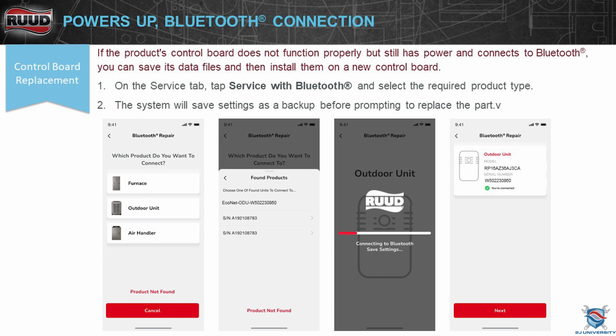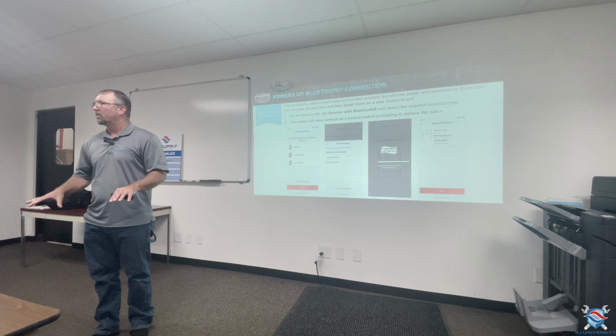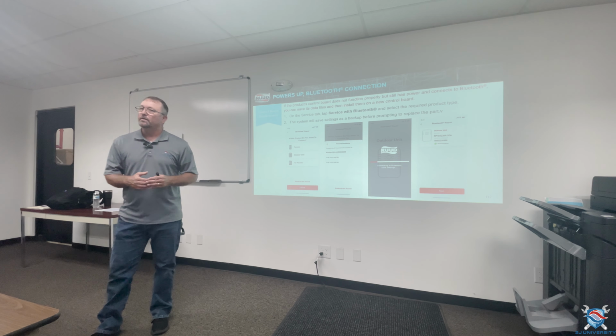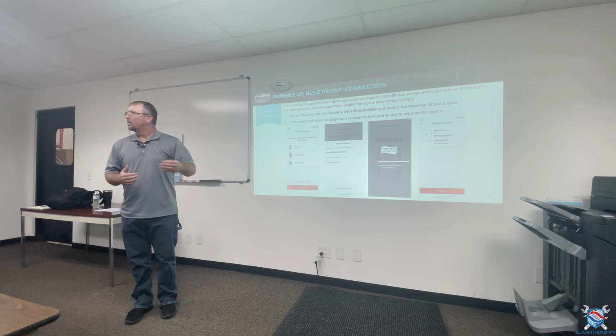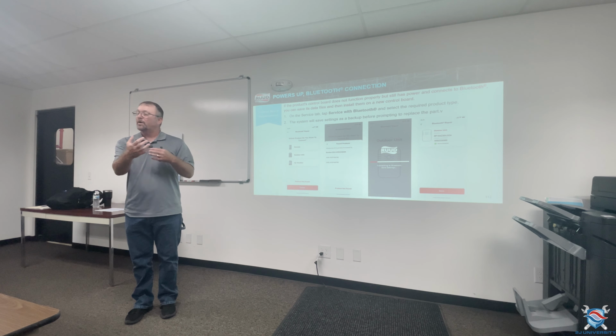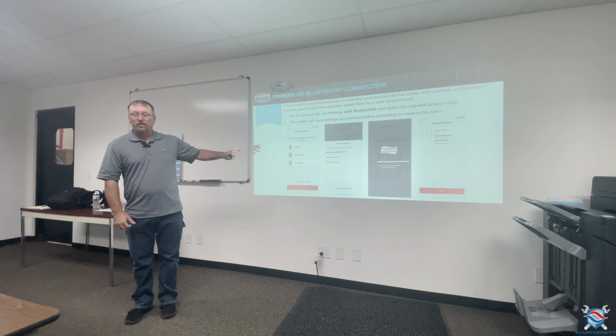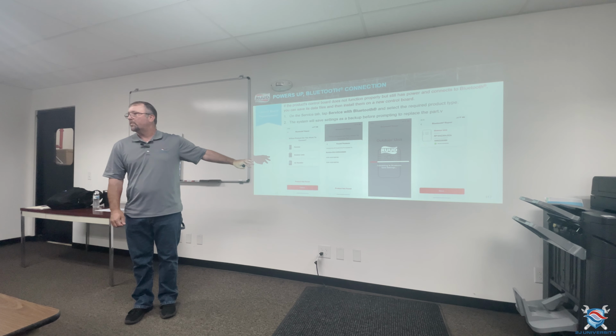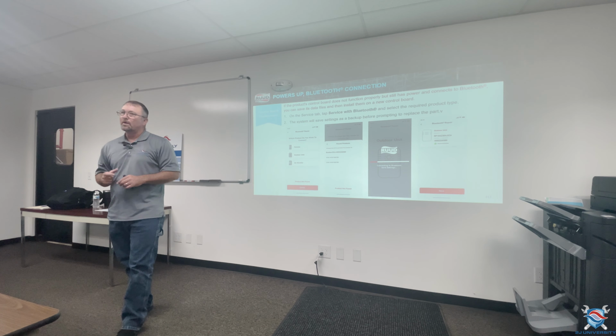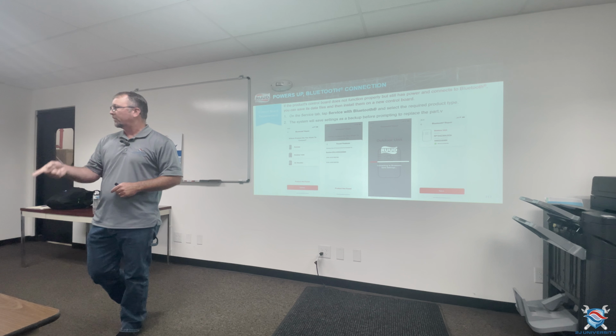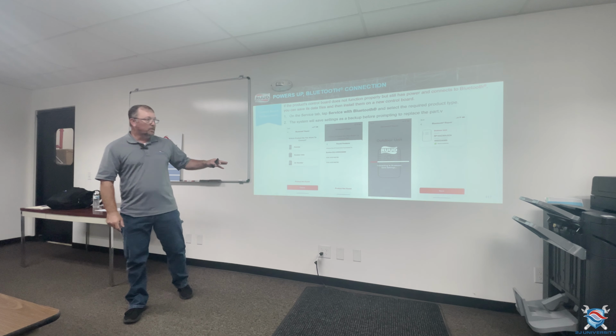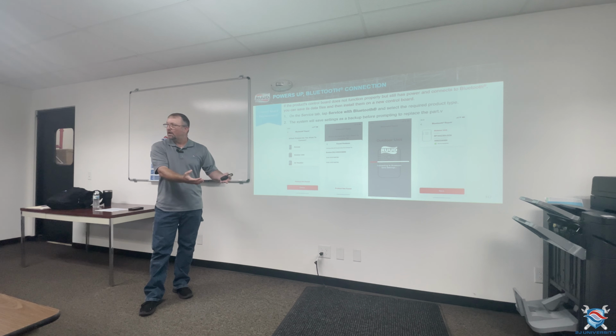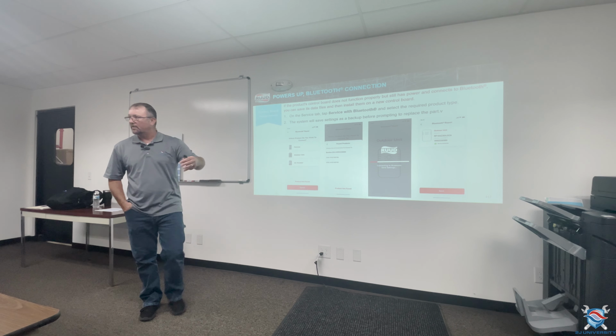So, for example, I go out to the unit and it's got a dead board on it. It will not power up the board. You can do this manually, but there are a few more steps involved. You manually put in the serial number and it pulls the data, because all serial numbers are put into this Contractor App on a daily basis. So for every furnace, it knows by serial number what the parameters were set to from the factory. When you're going through it manually, you put in the serial number and it uploads that information, but there are some more steps involved.